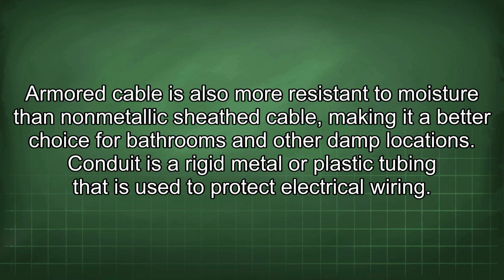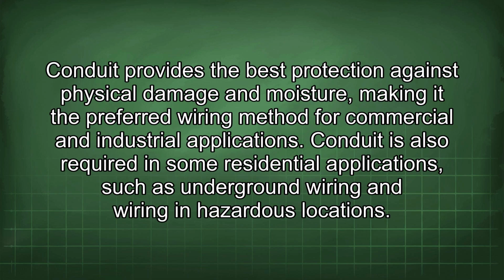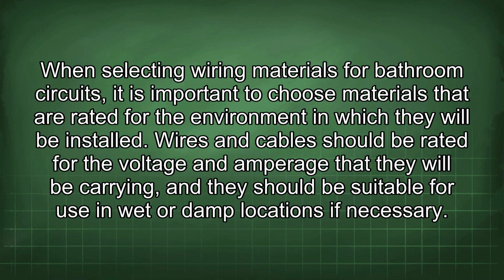Conduit is a rigid metal or plastic tubing that is used to protect electrical wiring. Conduit provides the best protection against physical damage and moisture, making it the preferred wiring method for commercial and industrial applications. Conduit is also required in some residential applications, such as underground wiring and wiring in hazardous locations. When selecting wiring materials for bathroom circuits, it is important to choose materials that are rated for the environment in which they will be installed.